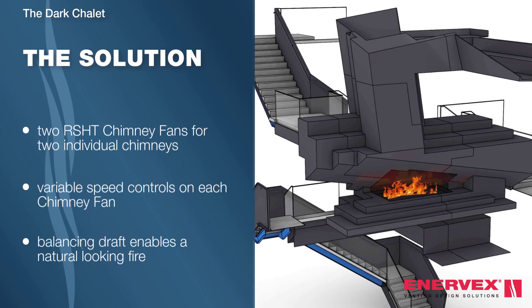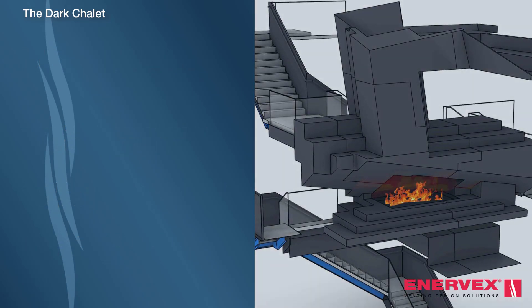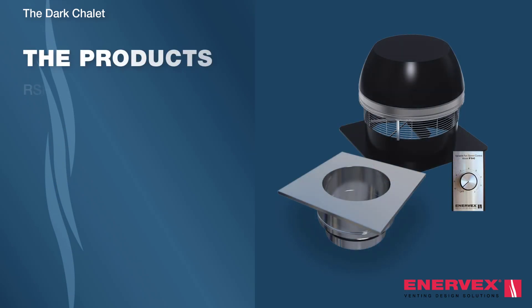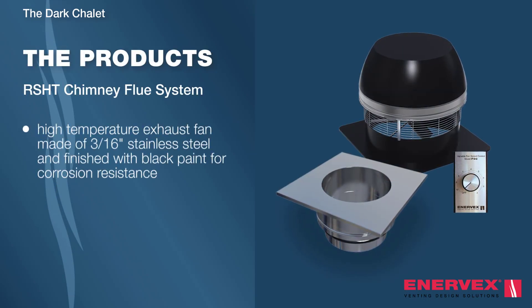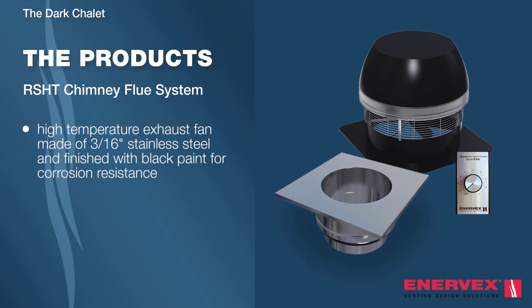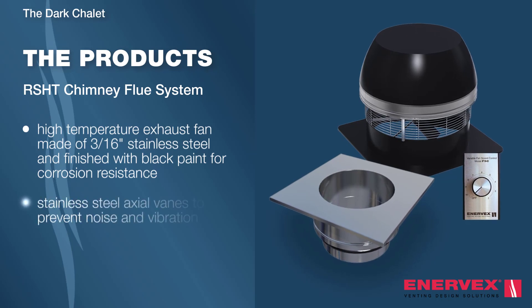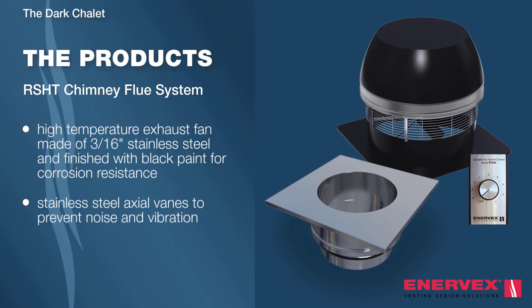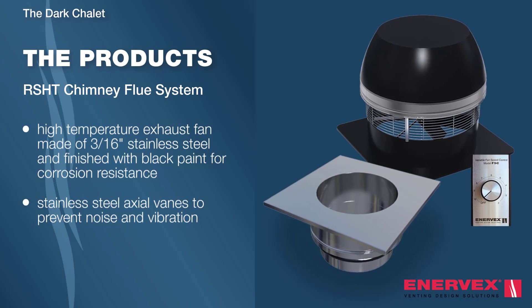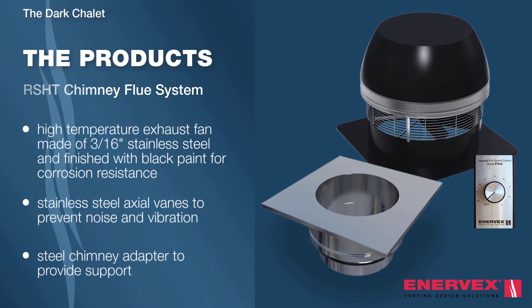The Enervex solution enables a fire free of unwanted noise and vibration. The RS-HT chimney fan is a high-temperature exhaust fan, made of stainless steel and finished with black paint for extra corrosion resistance. Stainless steel axial vanes assure low noise level and vibration-free operation. A steel chimney adapter is mounted at the chimney termination point to provide support.